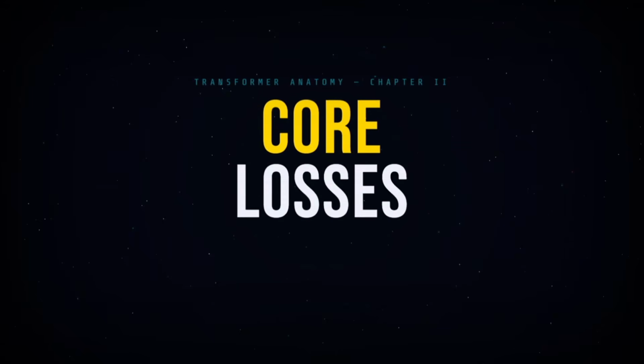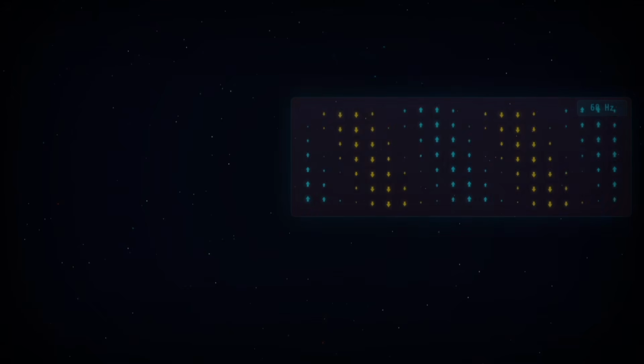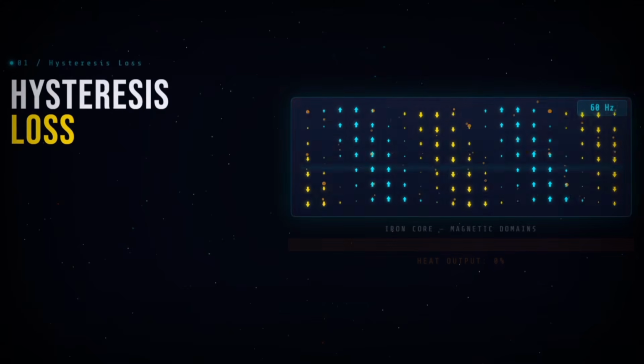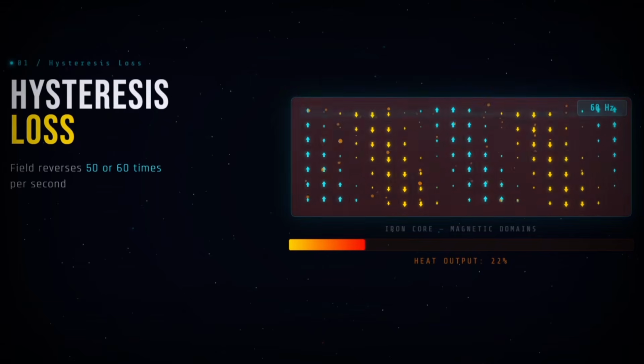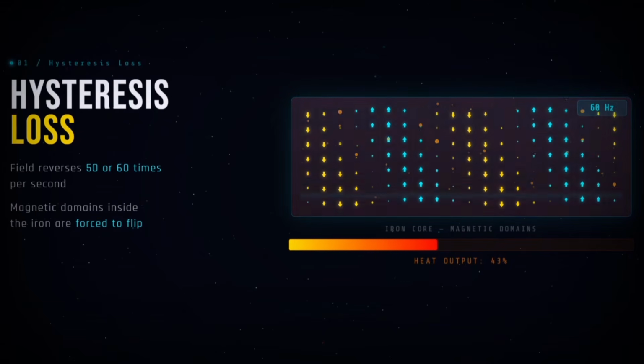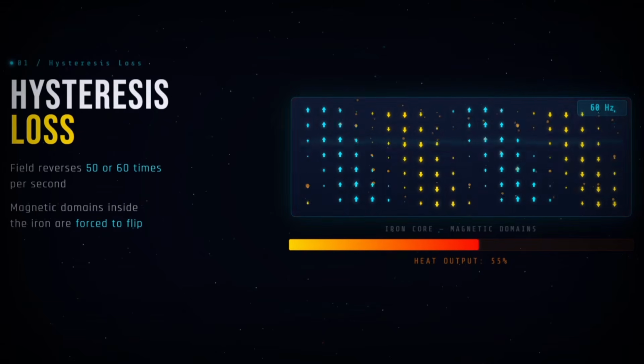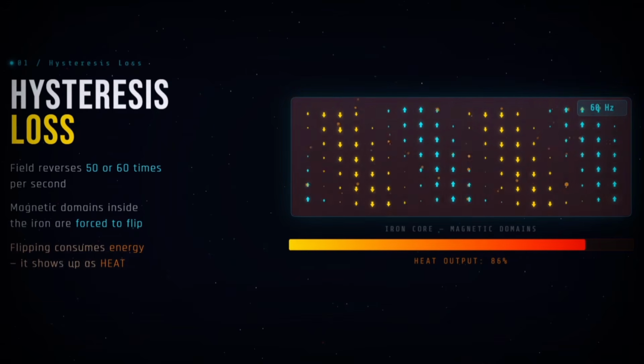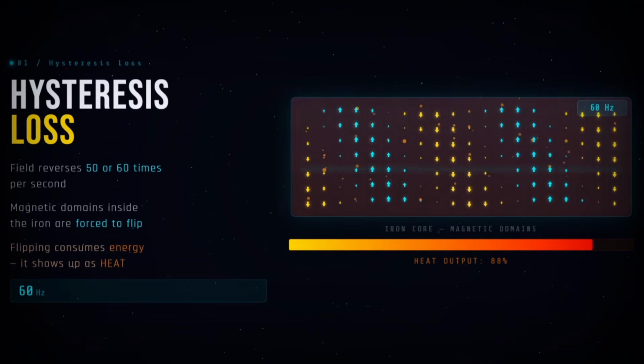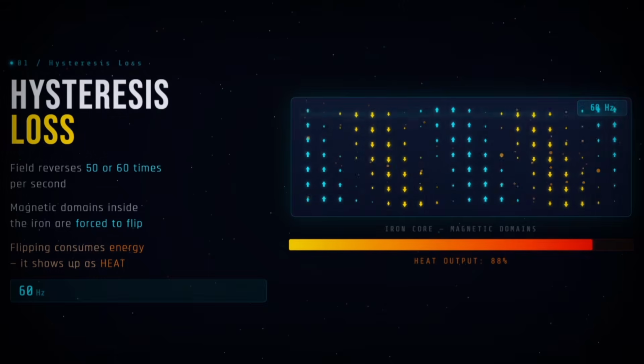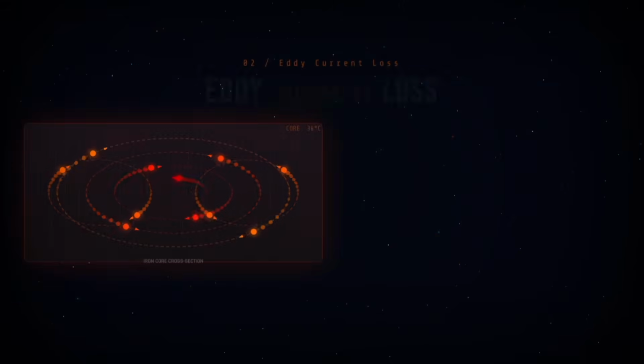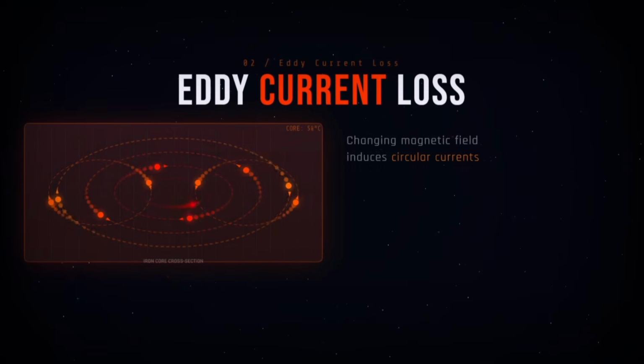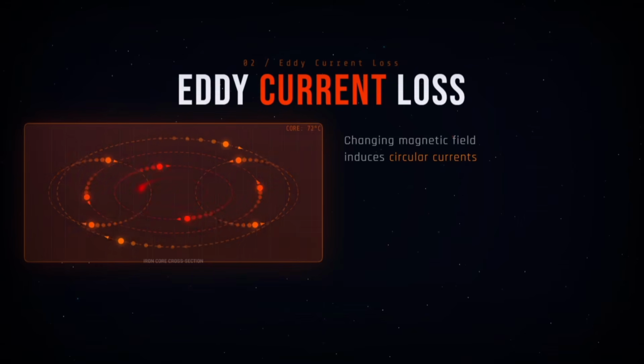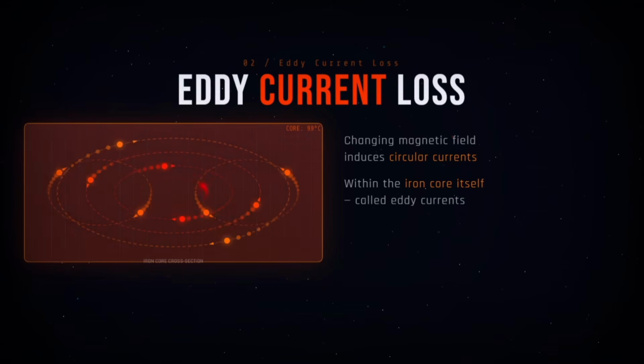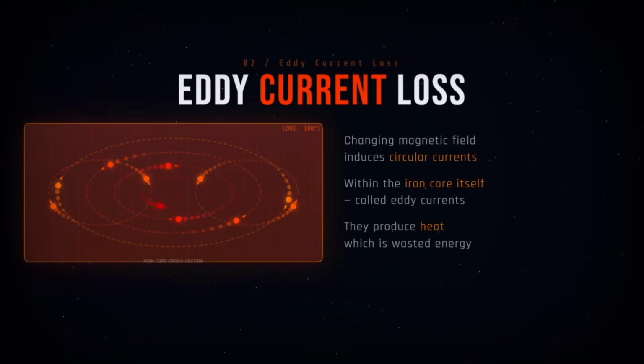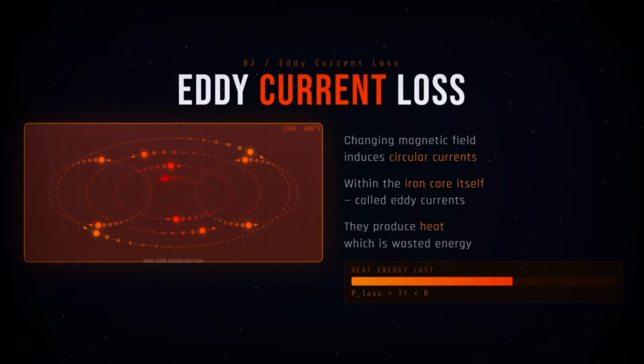Second, core losses. These come in two forms. Hysteresis loss: every time the magnetic field in the iron core reverses direction, 50 or 60 times per second, the tiny magnetic domains inside the iron have to flip. This takes energy and shows up as heat. Eddy current loss: the changing magnetic field also induces small, circular currents within the iron core itself, called eddy currents. They produce heat, which is wasted energy.